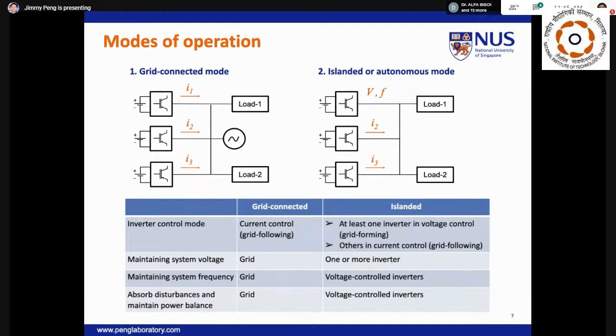utility network. On the other hand, islanded mode refers to when the microgrid has to provide its own voltage and frequency regulations. This is achieved by incorporating additional control loops in some of the inverters, and one popular method is droop control. Under islanded mode or autonomous mode, all instability issues must be handled by the grid-forming inverters, which are taking the role of the utility grid. Things become quite interesting under islanded mode, and this has sparked much research in addressing the microgrid stability in the context of regulating and power sharing capability.